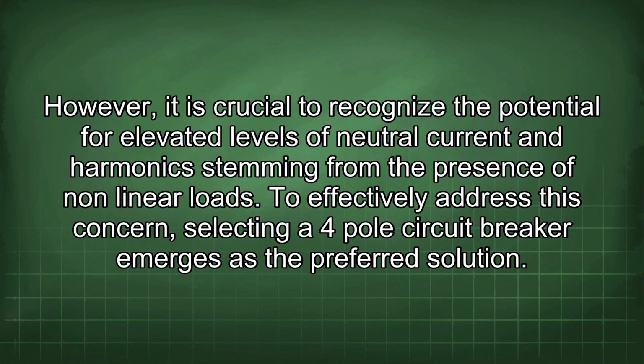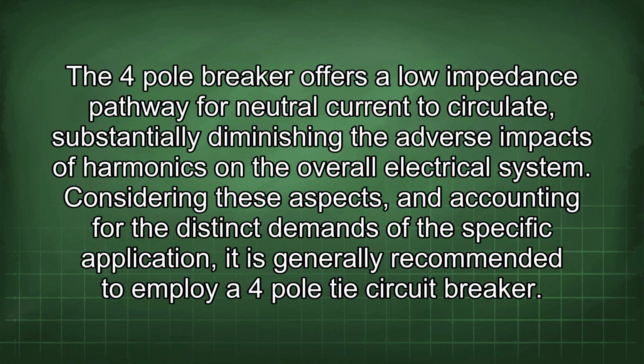However, it is crucial to recognize the potential for elevated levels of neutral current and harmonics stemming from the presence of nonlinear loads. To effectively address this concern, selecting a 4-pole circuit breaker emerges as the preferred solution. A 4-pole breaker offers a low impedance pathway for neutral current to circulate, substantially diminishing the adverse impacts of harmonics on the overall electrical system.